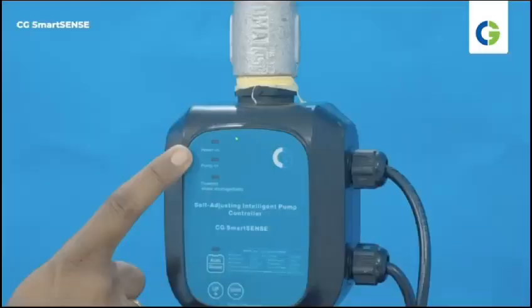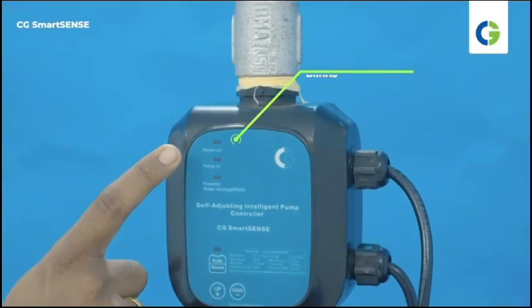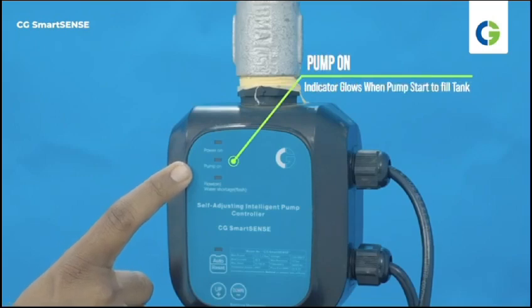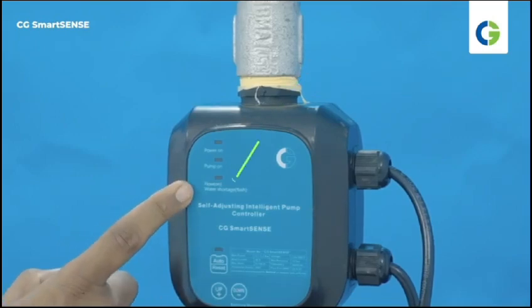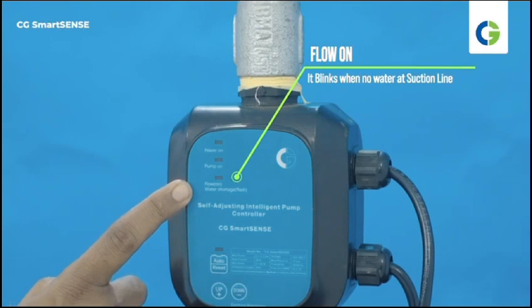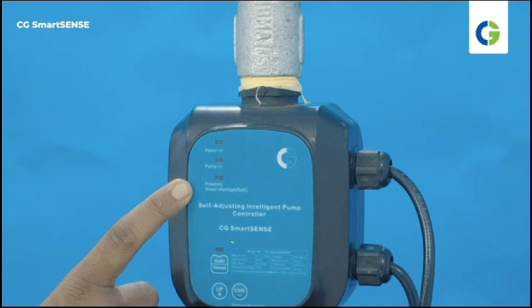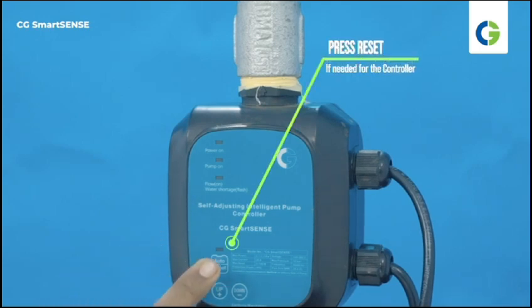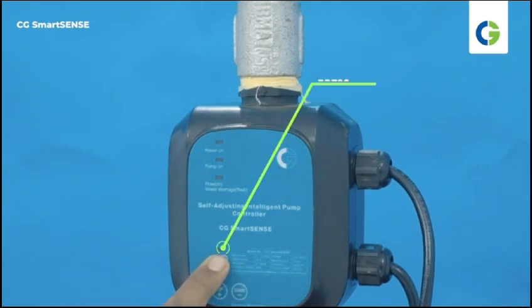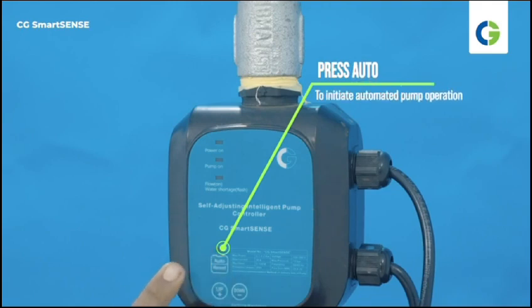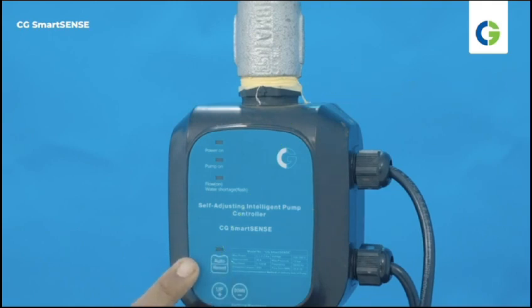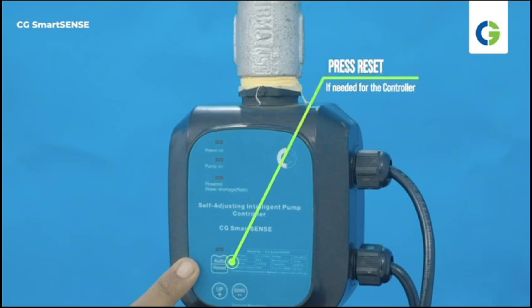You must know about the controller that you are going to use. Power on blinks when the supply is on. Pump on will blink when the pump is operating to fill the tank. Flow on will blink when there is no water flow from the source. In that case, check water availability in the suction line. If water is available, then inspect the flow sensor for blockages due to foreign substance entry into it. Press reset on the controller if needed. Auto button. To initiate automated pump operation based on sensor readings, press the auto button. Use the reset button if the controller shows an error or malfunctions.